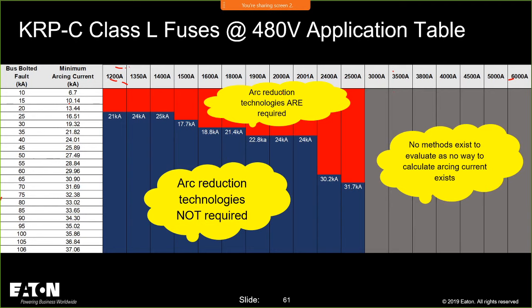This is what we use for our tool. I know that for a 1200 amp fuse, I need at least 21,000 amps of bolted fault current to get into the 0.07 second time. Now this is 480 volts, not 208 volts. I don't have a table for 208 volts, but you can use the app.